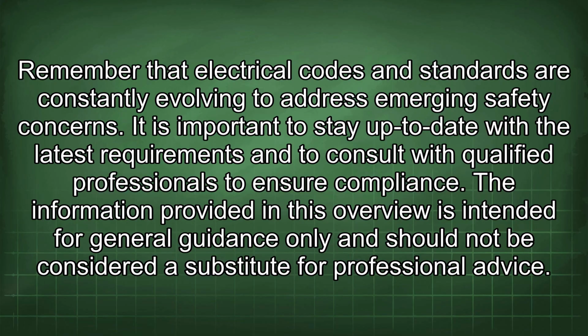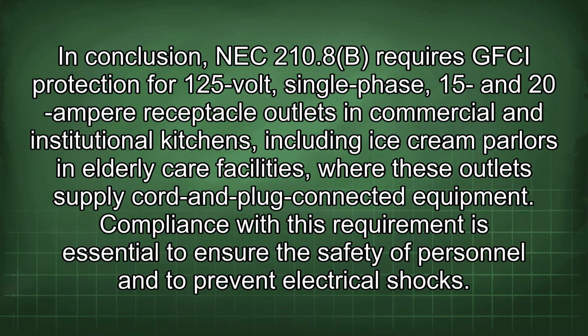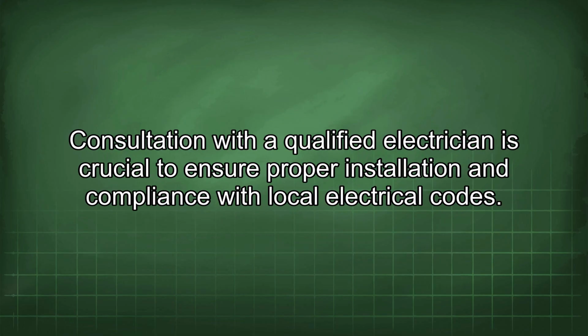In conclusion, NEC 210.8b requires GFCI protection for 125-volt, single-phase, 15 and 20 ampere receptacle outlets in commercial and institutional kitchens, including ice cream parlors and elderly care facilities, where these outlets supply cord and plug-connected equipment. Compliance with this requirement is essential to ensure the safety of personnel and to prevent electrical shocks. Consultation with a qualified electrician is crucial to ensure proper installation and compliance with local electrical codes.